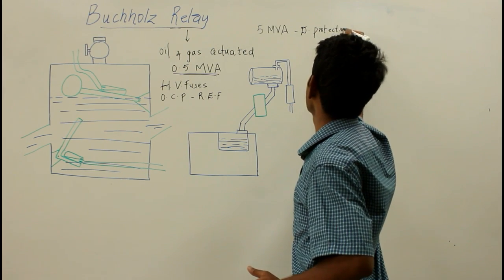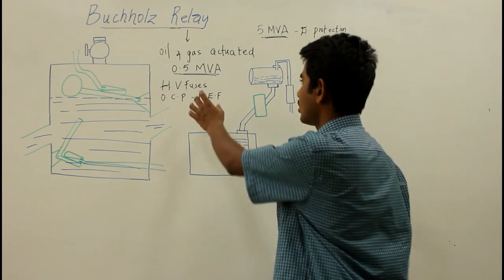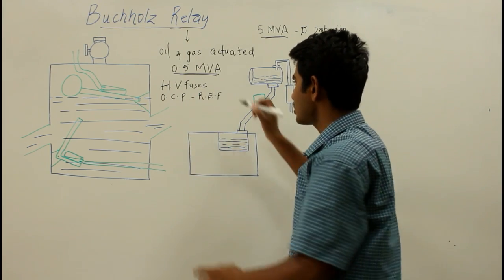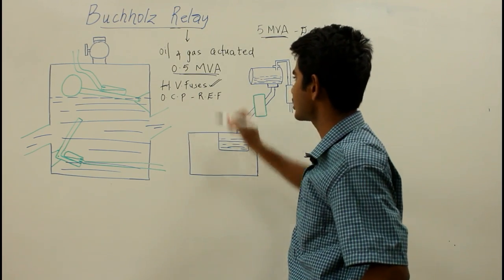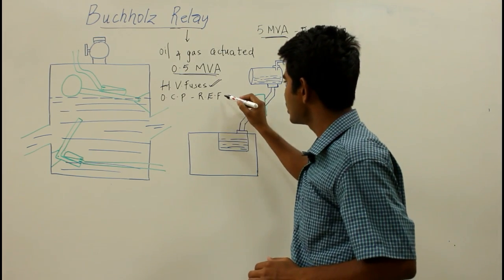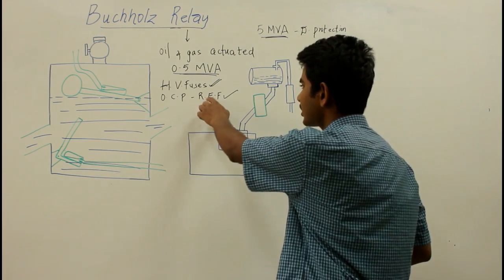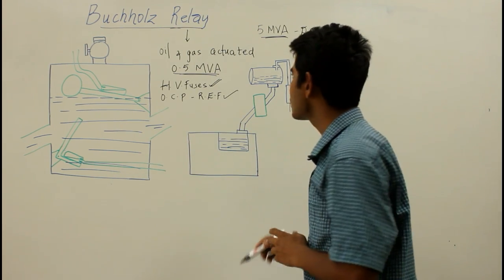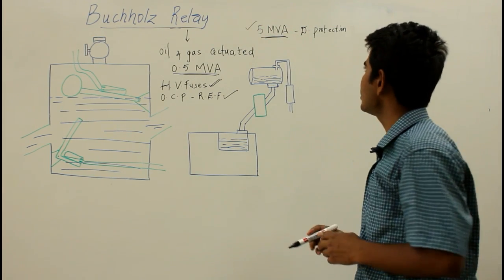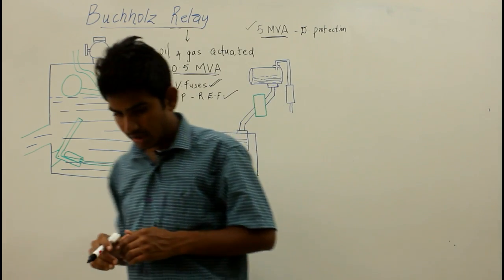For transformers with a rating more than 5 MVA, differential protection can be used. To summarize: below 0.5 MVA, high voltage fuses are used; for large and important distribution transformers, overcurrent protection along with restricted earth fault protection is used; and for higher rated transformers above 5 MVA, differential protection can be used.